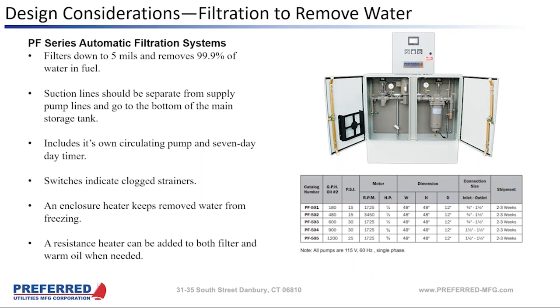What I do is I set up polishers to only run during the day shift, because sometimes the night shift people are pretty busy or sketchy and don't have the level of training that day shift people do. So I don't like moving fuel other than on the day shift if it's voluntary polishing like this. And as far as how often to run your polisher, in the Southeast, it depends on your weather. It depends on how humid it is and what your temperature variations are. Because here in the Southeast, you wake up some mornings and it looks like it's rained, but it hasn't. It's just that the ground cooled off overnight with very moist air, and it condensed water all over your car and the road and everything else, making it look like it rained. And that's going to do the same thing inside your tanks.